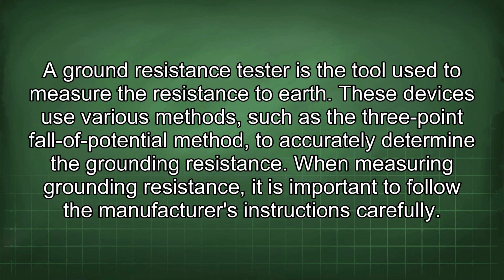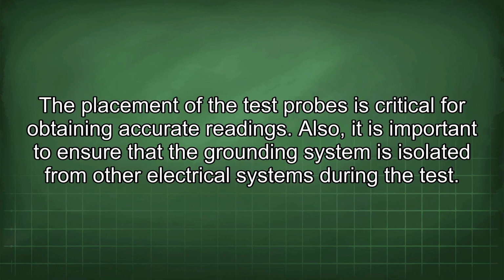When measuring grounding resistance, it is important to follow the manufacturer's instructions carefully. The placement of the test probes is critical for obtaining accurate readings. Also, it is important to ensure that the grounding system is isolated from other electrical systems during the test.